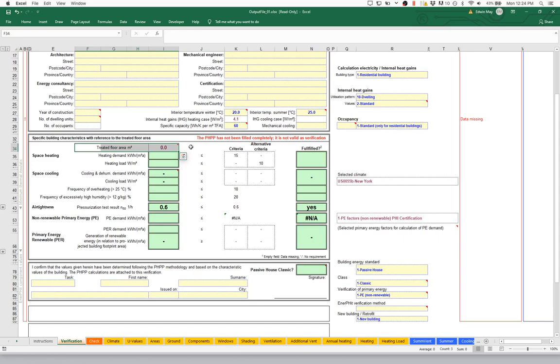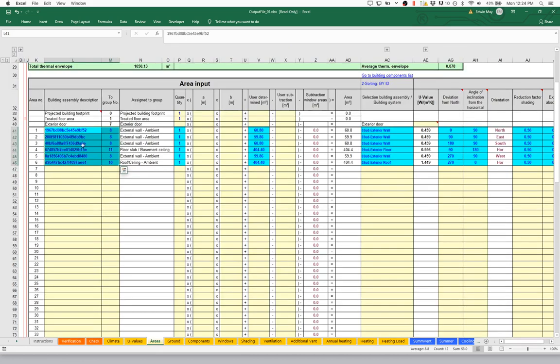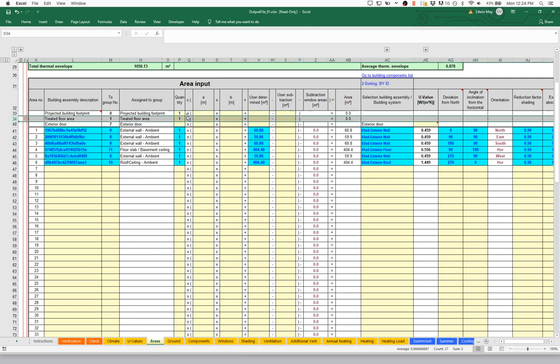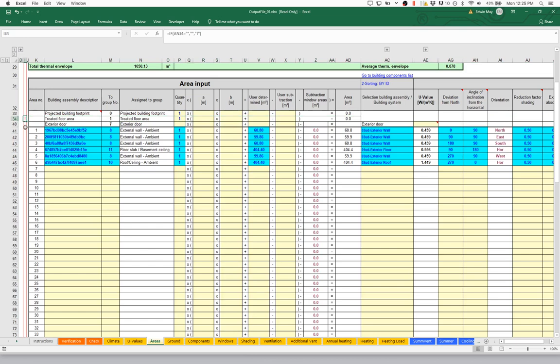So why is the treated floor area still zero? After all, don't we have a floor in our building — haven't we pushed that through? The treated floor area gets entered on row 34 of the areas worksheet. We can either enter a length and a width, or pass in a single value representing the total floor area. Notice these are all blank — we don't have any inputs for our treated floor area. PHPP gives us a little warning that there's an error on this row that we need to resolve.